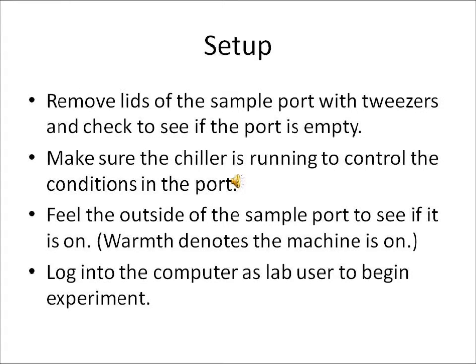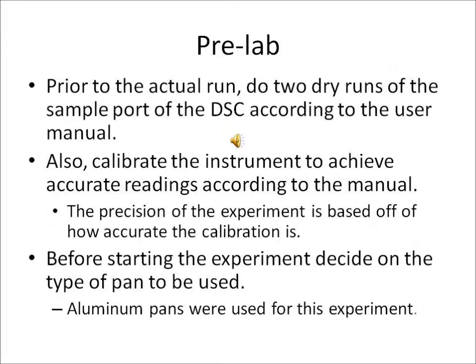When setting up the DSC, remove the lids of the sample port with tweezers and check to see if the port is empty. Make sure the chiller is running to control the conditions of the port. Feel the outside of the sample port to see if it is on. Warmth denotes the machine is on. Log into the computer as lab user to begin the experiment.